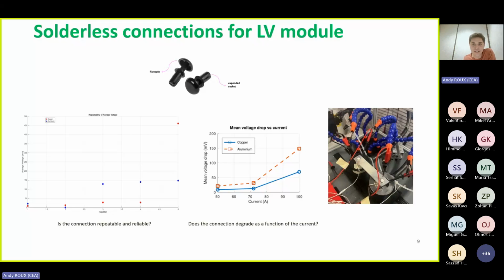Since the beginning, I've only shown you what was good, where the connections were good. But for this one, that wasn't the case. On this test, I did 5 repetitions on each connection because I wanted to see if it was reliable. On the first 2 tests I was around 20 millivolt drop, which was our threshold inside the specification, but I wasn't sure about the repeatability. So I made 5 tests, and what we see is a lot of dispersion around the value we got. The conclusion was that the solution wasn't good for the application — it's not really reliable or repeatable.